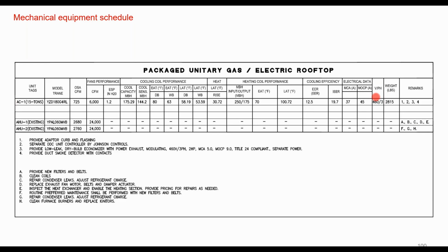So good for everyone. There's a question, the note for number 3, that is the power exhaust. That is only 2 horsepower, but it doesn't actually give us the main supply fan horsepower. So good catch on that. But yeah, we're still missing total fan power in this example. So again, you might have to be digging for more information, even on a compliance model where you have a full set of drawings.